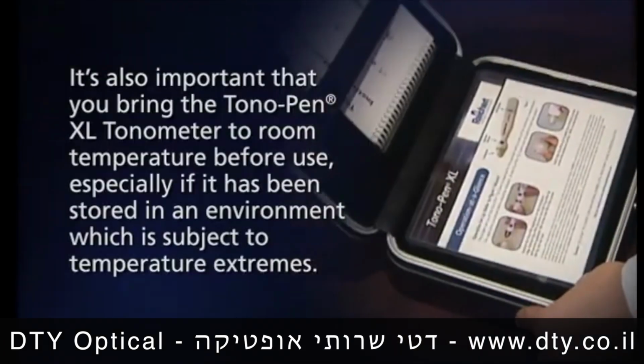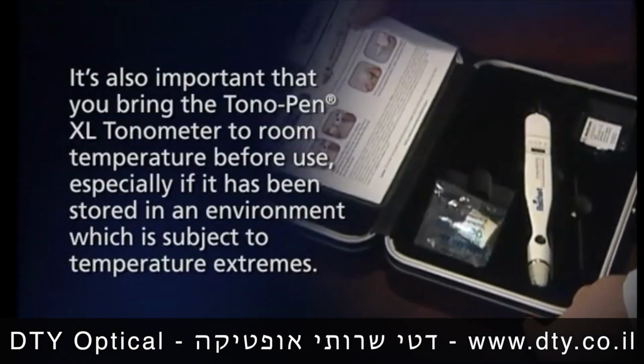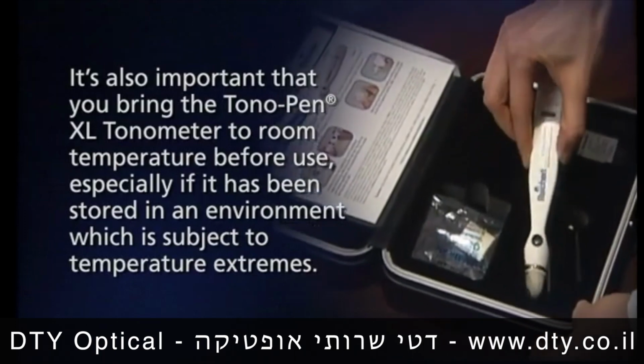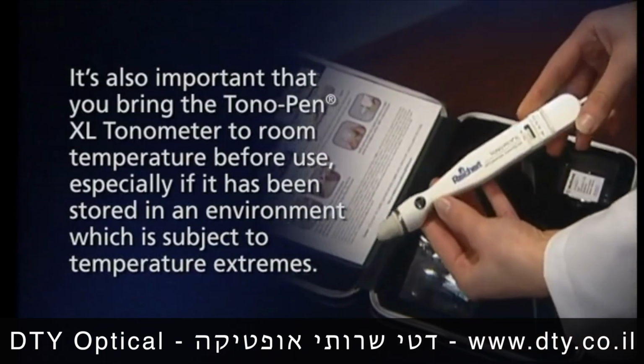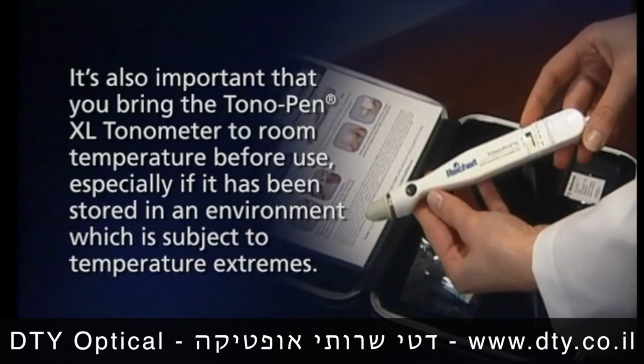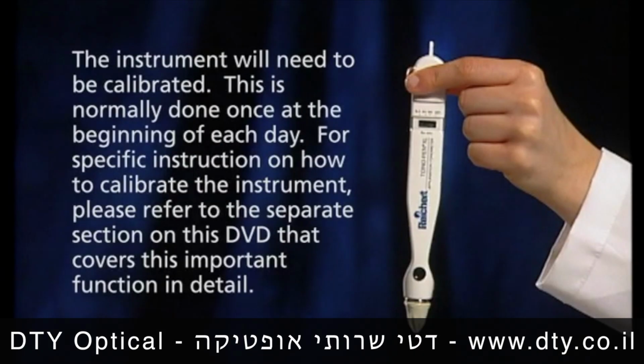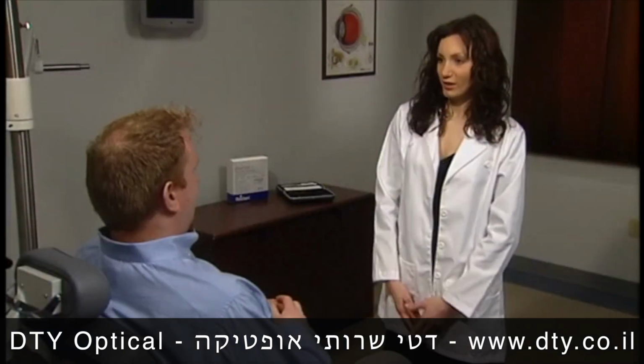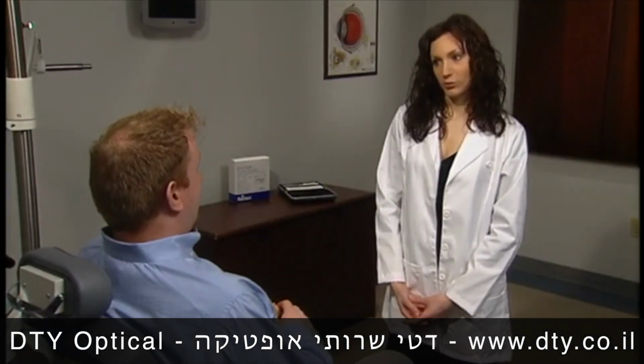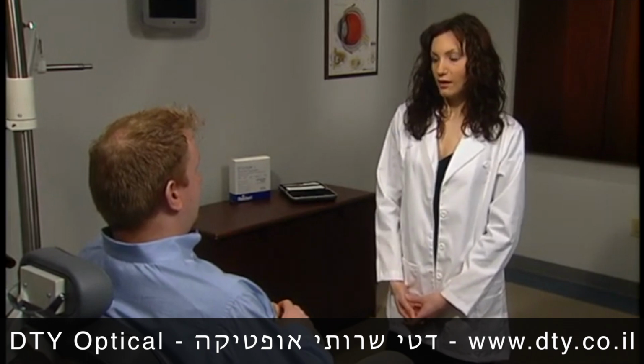It's also important that you bring the TonoPen XL tonometer to room temperature before use, especially if it's been stored in an environment which is subject to temperature extremes. Finally, the instrument will need to be calibrated. This is normally done once at the beginning of each day. For specific instruction on how to calibrate the instrument, please refer to the separate section on this DVD that covers this important function in detail. If you are sure that the instrument is correctly calibrated and your patient is prepared, you are now ready to perform the measurement.